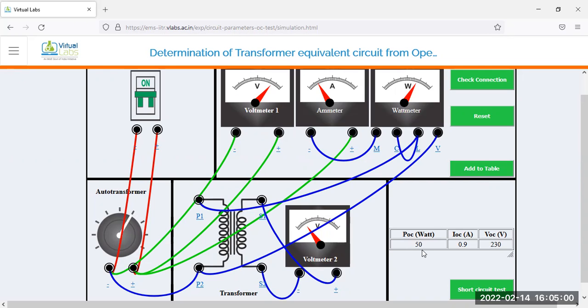So all the parameters you may find in the table form. So you will get the value of power consumption during the no load test, that means 50 watt, no load current 0.9 ampere, and 230 volt.